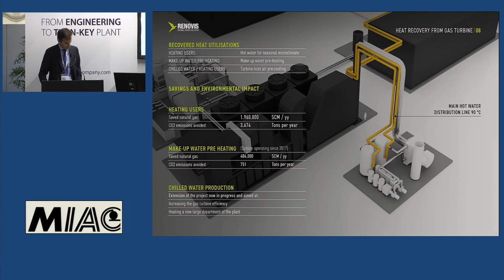This slide summarizes the saving results obtained from the first phase of implementation of the thermal recovery system we designed and built. The total savings for heating the semi-finished product storage warehouses and for preheating the make-up water of the recovery steam generator is approximately 2,400,000 standard cubic meters of natural gas, corresponding to approximately 4,400 tons per year of avoided climate-altering gas emissions.